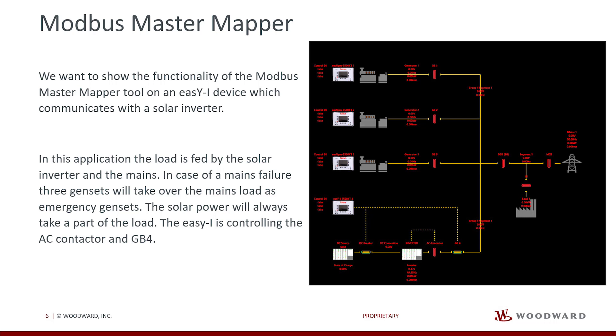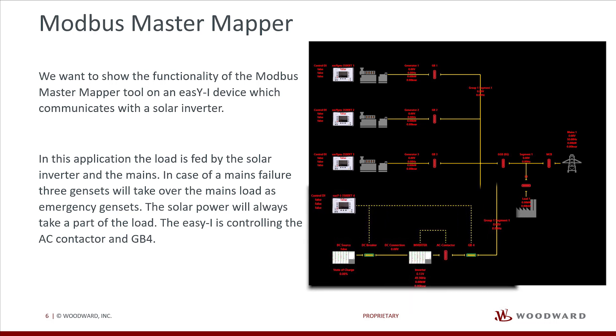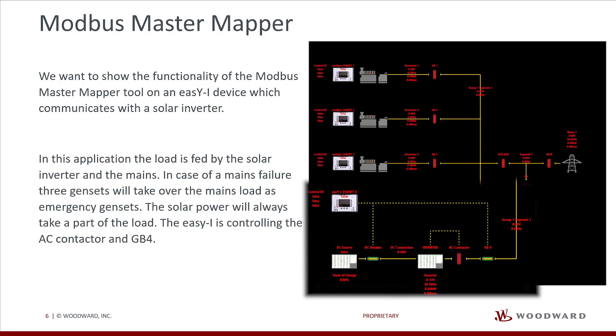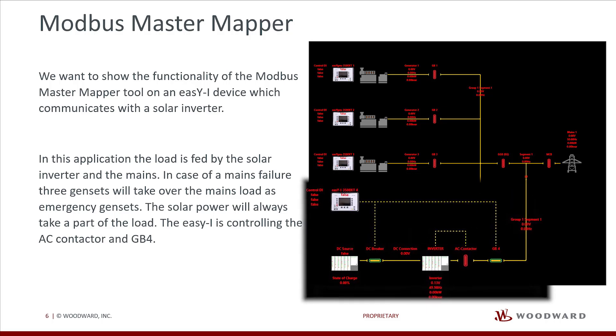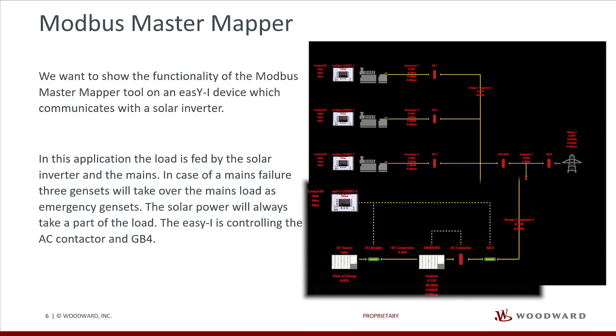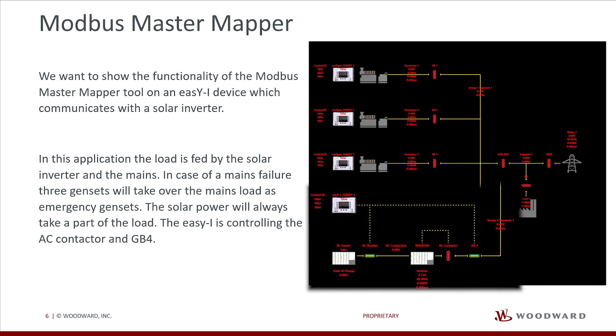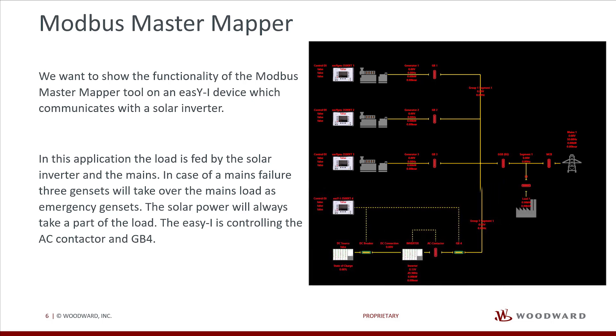In this application, the load is fed by the solar inverter and the mains. In case of a mains failure, three gensets will take over the mains load as emergency gensets. The solar power will always take a part of the load. The easy-I is controlling the AC contactor and GB4. It also manages the solar inverter and supplies a maximum of solar power to the application. For this, it acts as a Modbus Master in the application and receives data from the solar inverter.